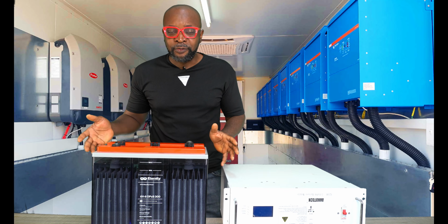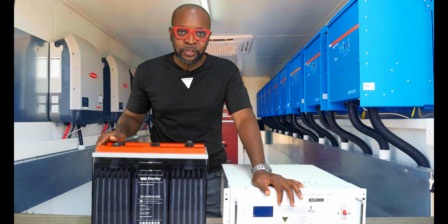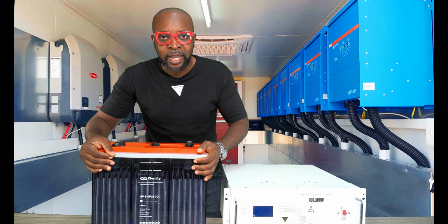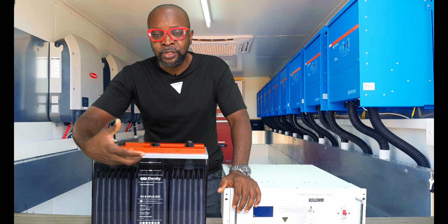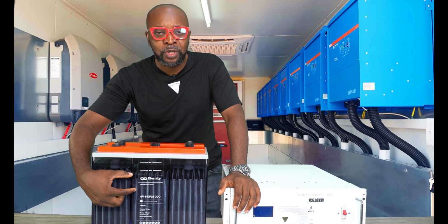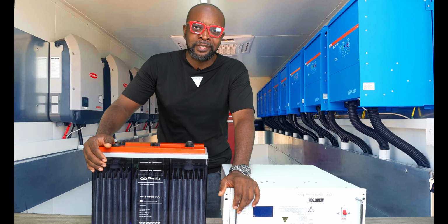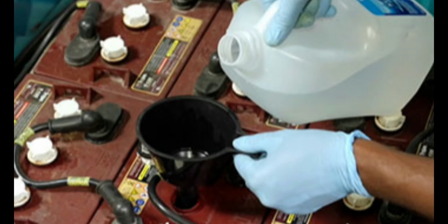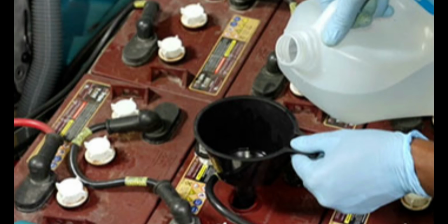Number one is you would have to hydrate the battery. After 6 months, the electrolyte level, you can see it from here, right? After around 6 to 7 months, the electrolyte is definitely going to go down. This happens because whilst the battery is charging, it releases hydrogen into the air, so the gas escapes. So you definitely have to hydrate the battery. You need to fill in distilled water into the battery.